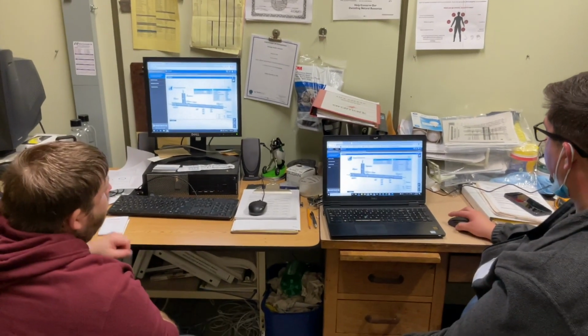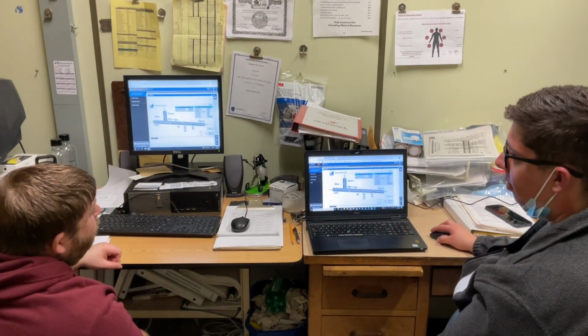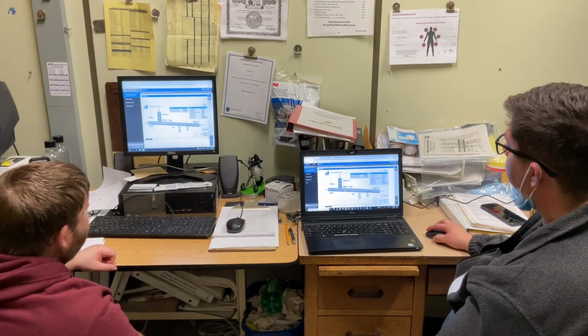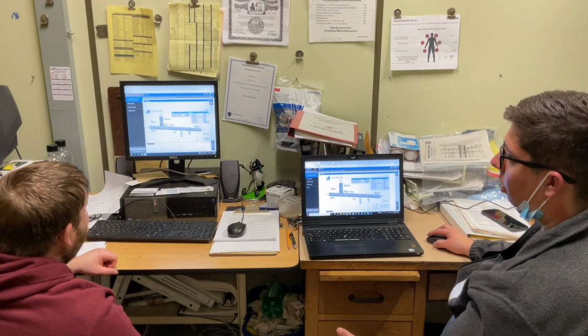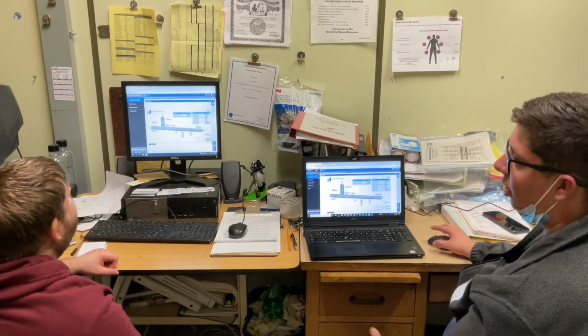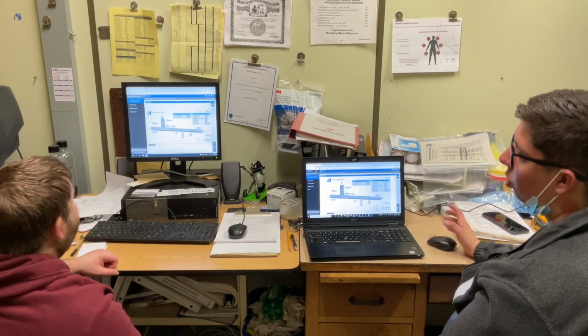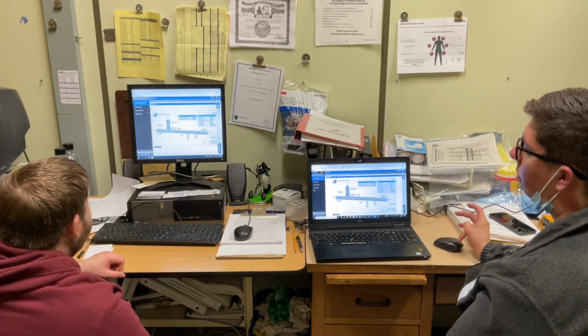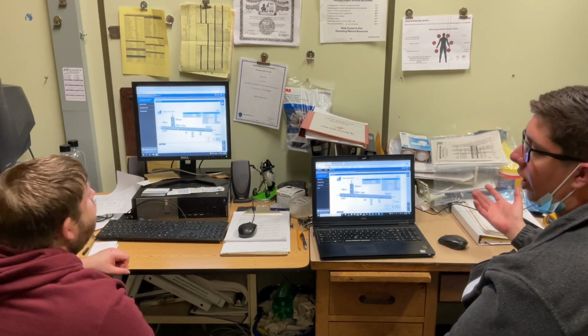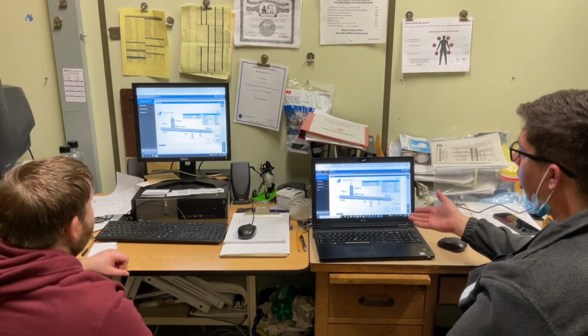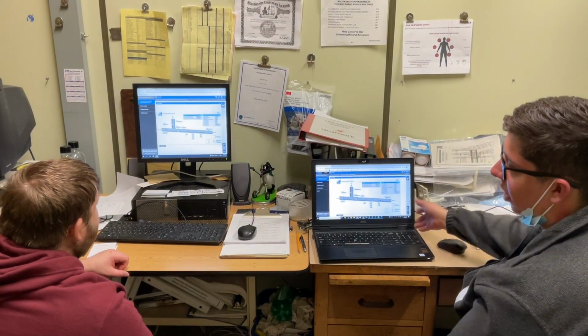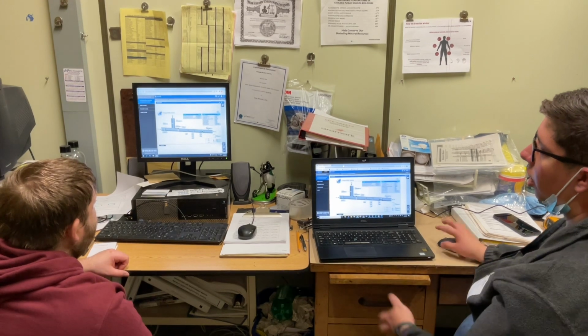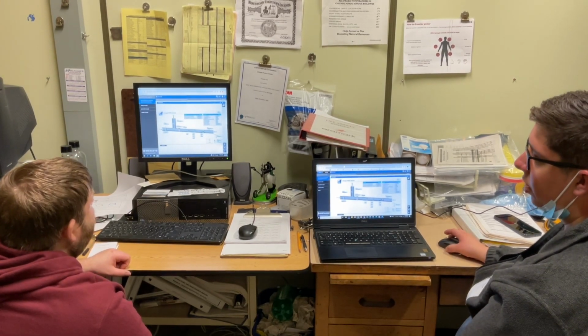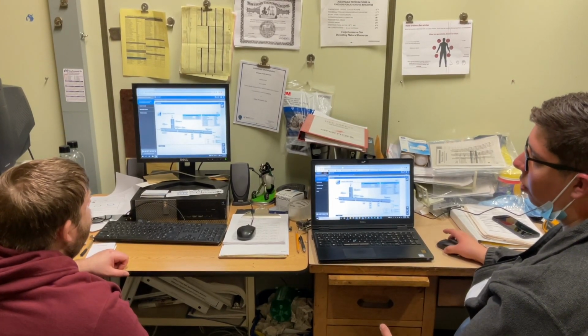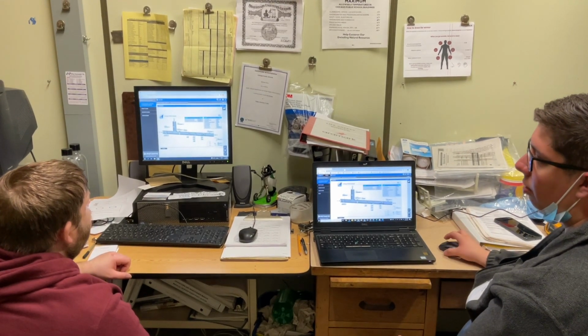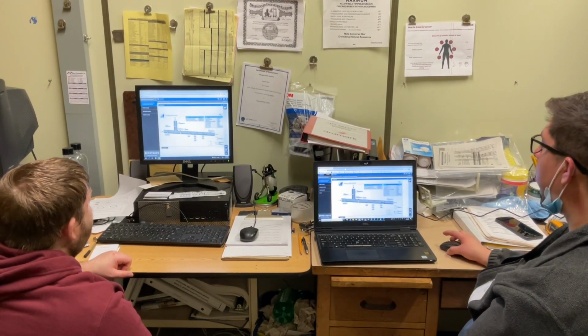The cooling enable and reheat enable, if these are false, even if there's a call for heat, it won't come on. That's like your shutdown on that. Or for the cooling, say maybe there's something wrong with that condensing riser, but we wouldn't know that because it's a separate system. You can always turn that off. You can set it to false, and even if there's a call for cooling, it's not going to try to turn on that cooling stage. Same goes for the heating.